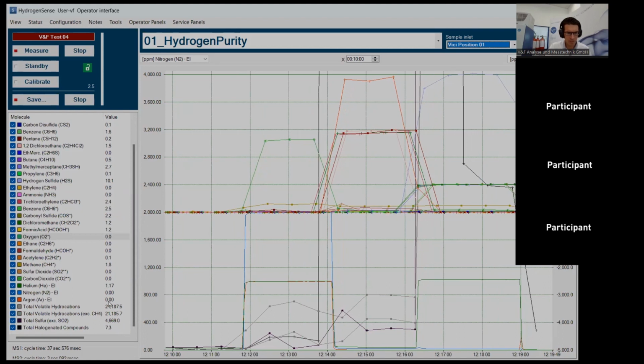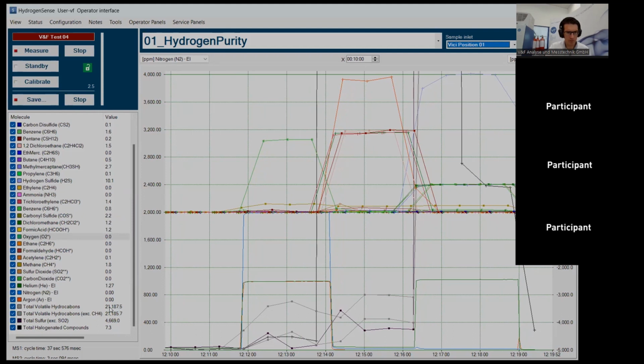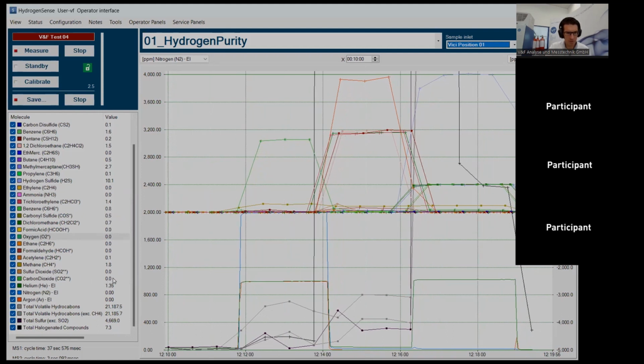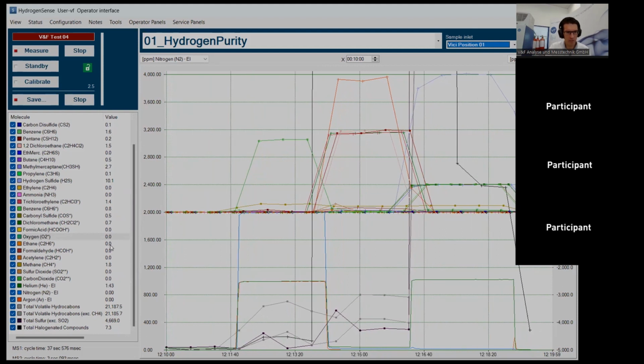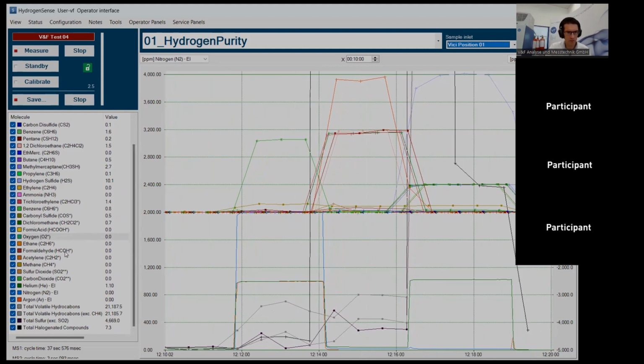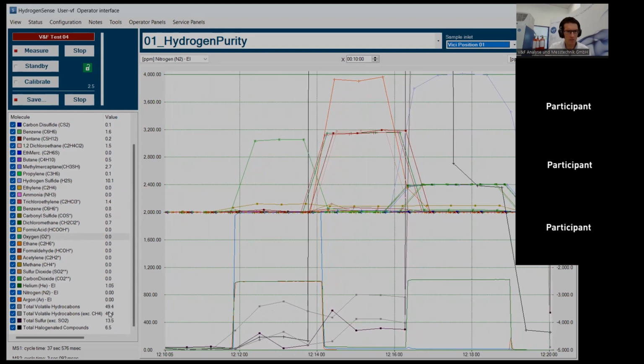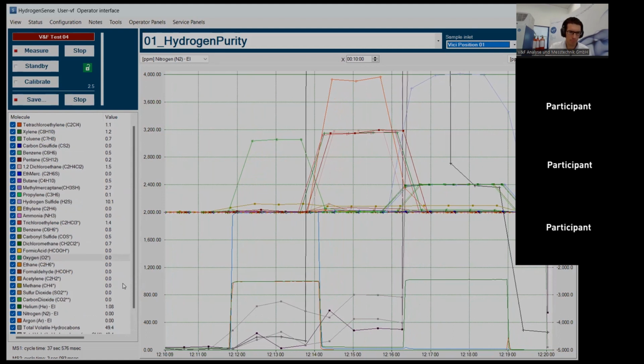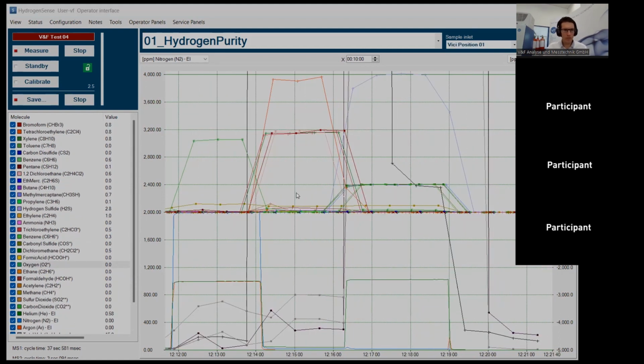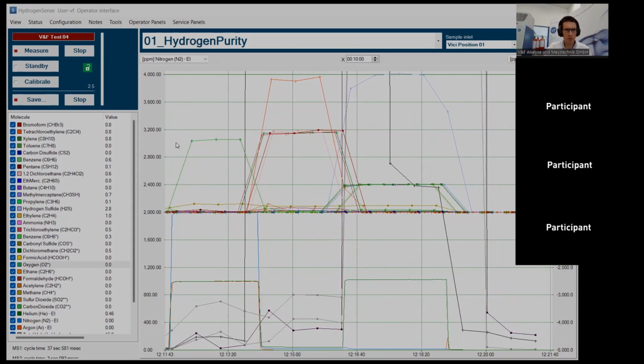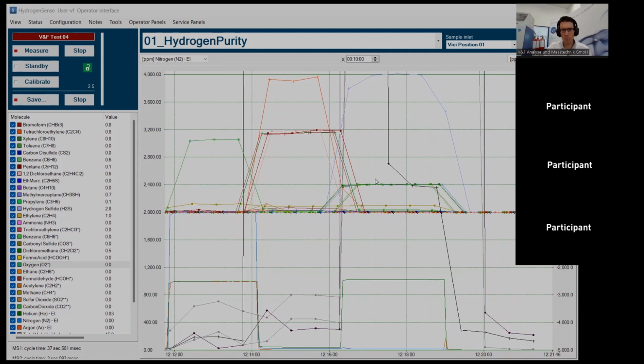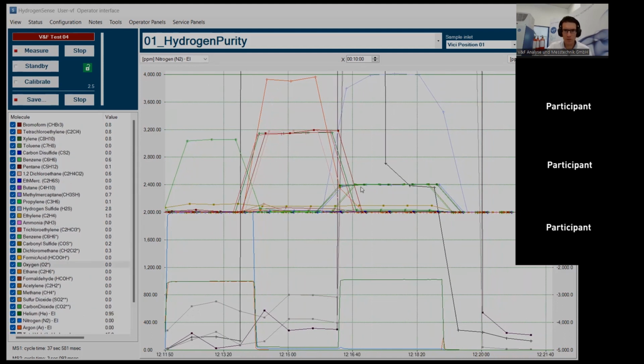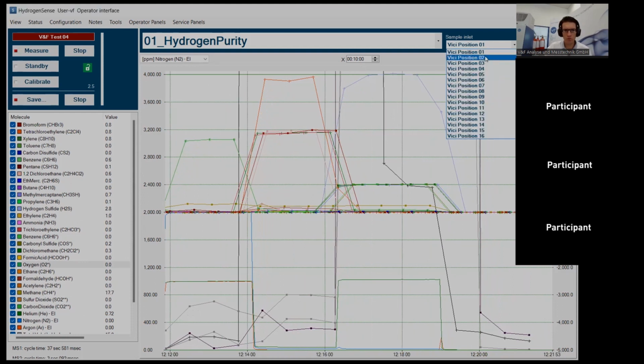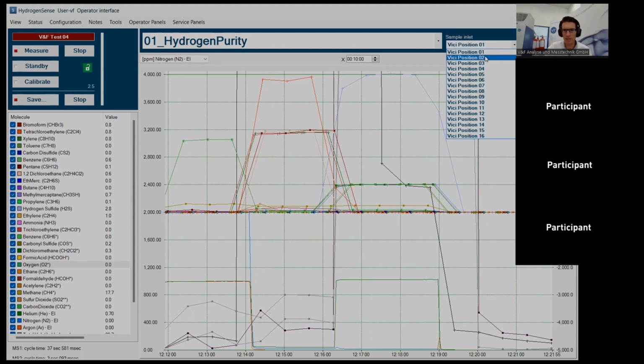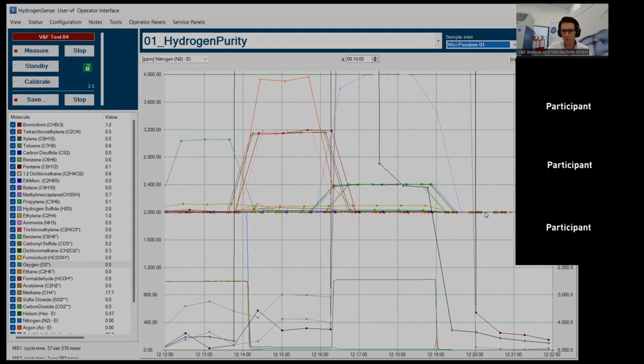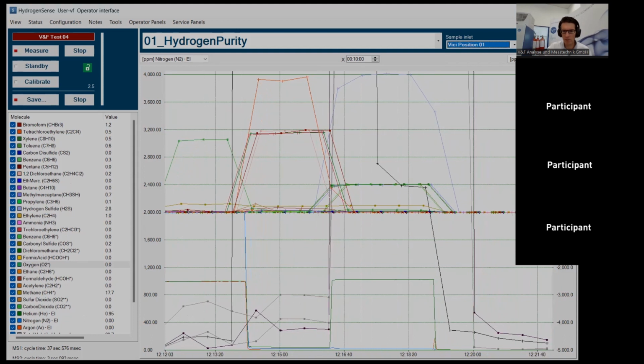And so you will see here, we still have a large number on that summation. This is because the summated values are only calculated once the measurement cycle is done. So once all the signals have been acquired, then the signal will go down. In principle, right now the instrument will always give you data, and it's pretty much just a matter of evaluating that data. So for example, if I'm going here, on position 2, I have a 5.0 standard hydrogen. In principle, what we are doing now is we are acquiring signal on the 6.0 standard.